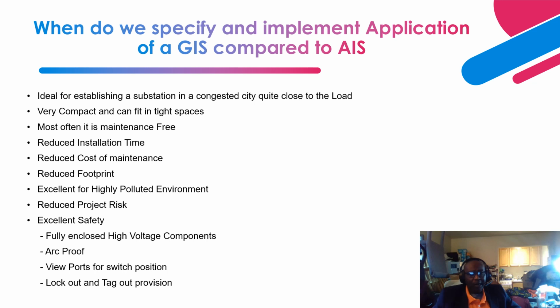So, comparably to an air insulated switchgear, where every year, every 3 years, every 6 years, for instance, you have to perform time-based maintenance, which basically requires a major outage and taking out a lot of the equipment. Look at the number of equipment that is in an AIS and its larger footprint. Basically it results in a lot of labor cost and parts cost. So basically, GIS is able to achieve a reduced cost of maintenance. And matter of fact, beyond that, it allows you to achieve a life cycle cost of maintenance, which is very good for life cycle modeling for your asset management for the GIS.